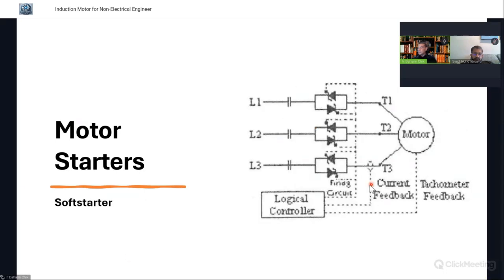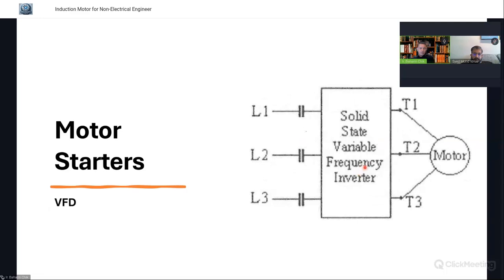Now this is the soft starter. Also, we have got three connections to the soft starter. We can run this soft starter using the power electronics that it provides. Now, in terms of solid state VFD, we also have 3 windings connected to the VFDs, and then from here we can set the frequency, the setting, the running of the motors accordingly.